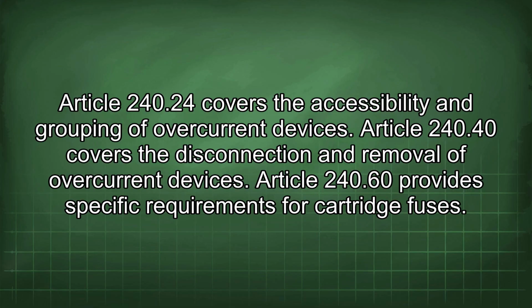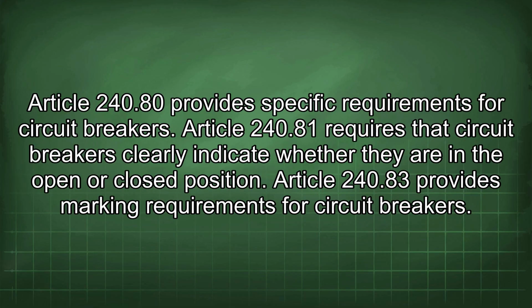Article 240.40 covers the disconnection and removal of overcurrent devices. Article 240.60 provides specific requirements for cartridge fuses. Article 240.80 provides specific requirements for circuit breakers. Article 240.81 requires that circuit breakers clearly indicate whether they are in the open or closed position. Article 240.83 provides marking requirements for circuit breakers.